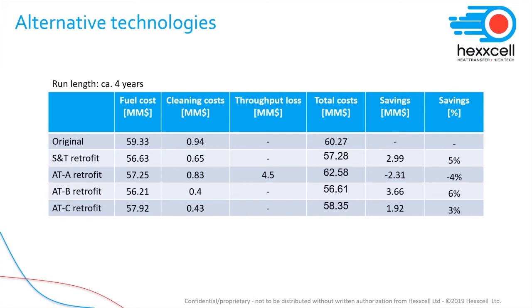So the key messages here are that the plant data can be used successfully to assess performance of alternative designs, but you need to be careful which design you pick to avoid loss in production or being too close to hydraulic limits. Moreover, this analysis should be done taking into account all interactions, thermal and hydraulic, between different heat exchangers in the network.